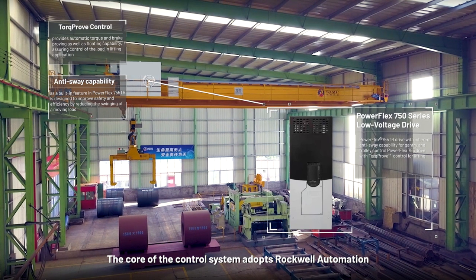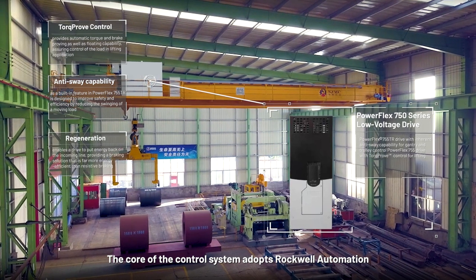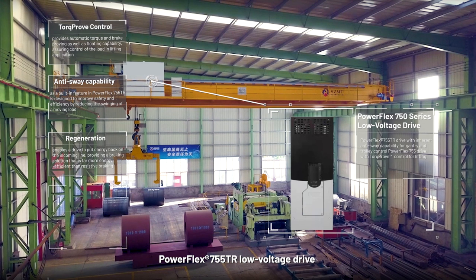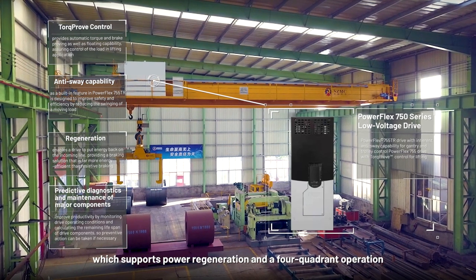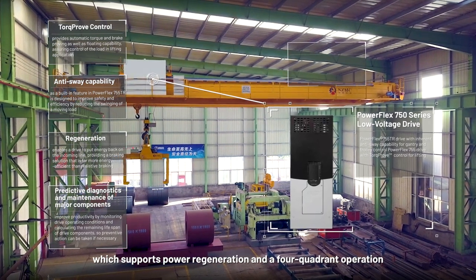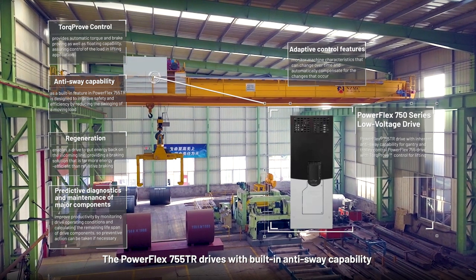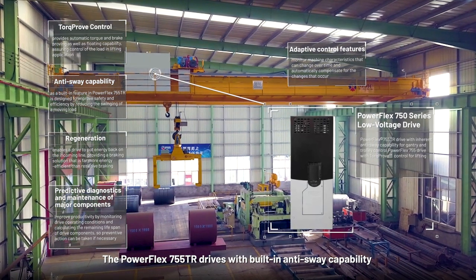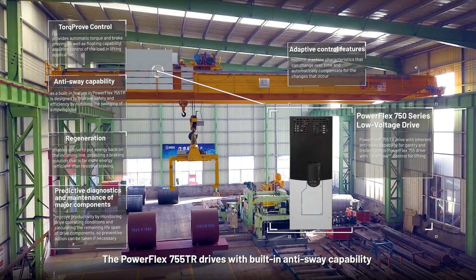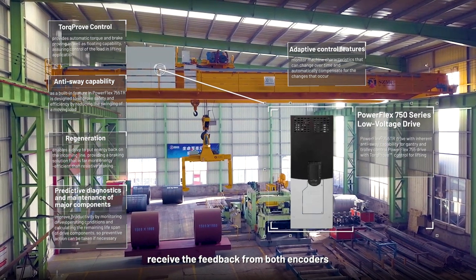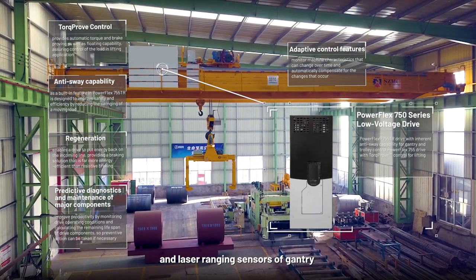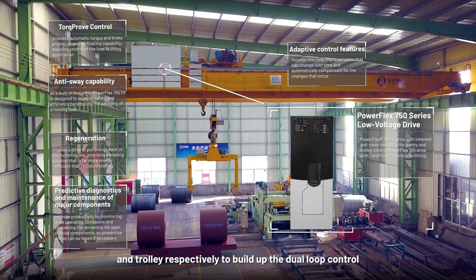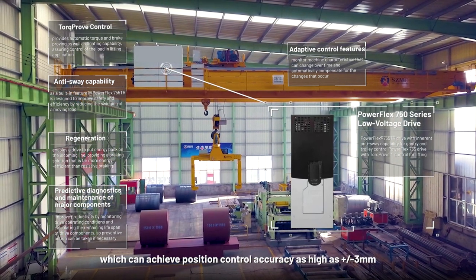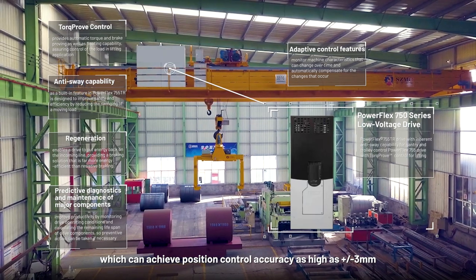The core of the control system adopts Rockwell Automation PowerFlex 755TR low voltage drive, which supports power regeneration and four quadrant operation. The PowerFlex 755TR drives with built-in anti-sway capability receive feedback from both encoders and laser ranging sensors of the gantry and trolley respectively to build up dual loop control, which can achieve position control accuracy as high as plus or minus 3 mm.